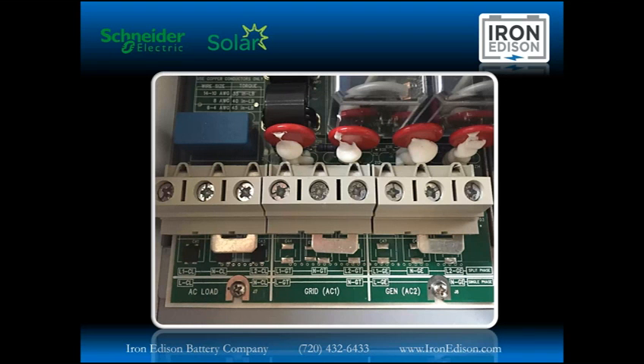We have wires landed on line 1 and the 3 different terminal slots. But what this just shows is that we have the AC load, which is the output side of the inverter, as well as grid and gen. So we have separate unique input ports for landing a backup generator and the grid.